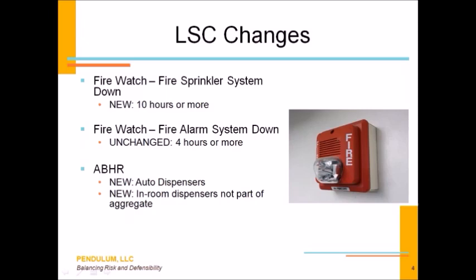When we made the switch from the 2000 edition of the Life Safety Code as enforced by CMS to the 2012 edition, there were definitely some changes you need to know about. So what I want to do now is highlight some of those changes with the Life Safety Code, NFPA 101, 2012 edition, and compliance with those codes. One of the significant changes is a change in fire watch requirements.